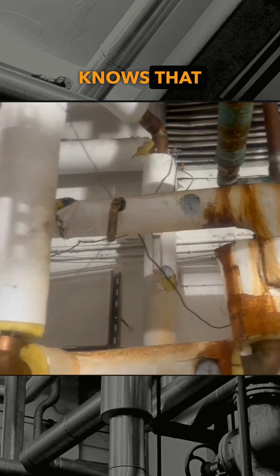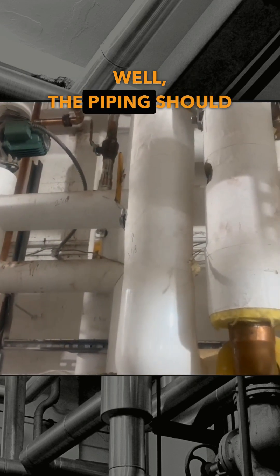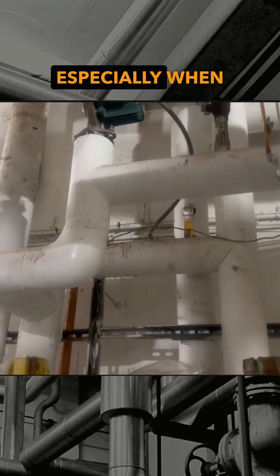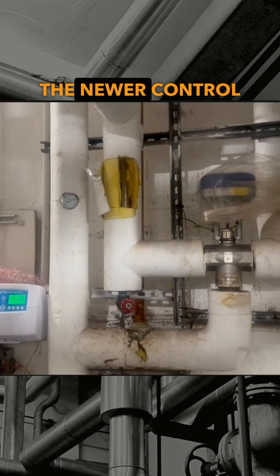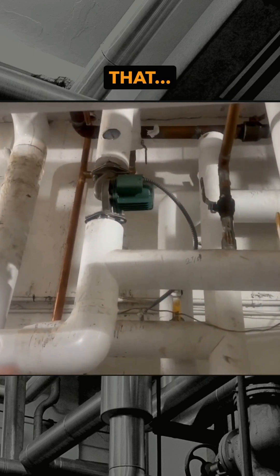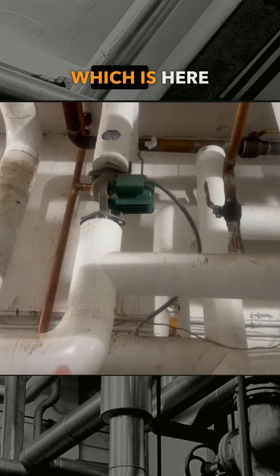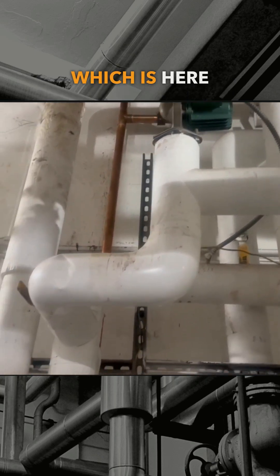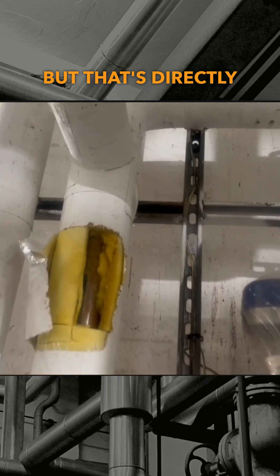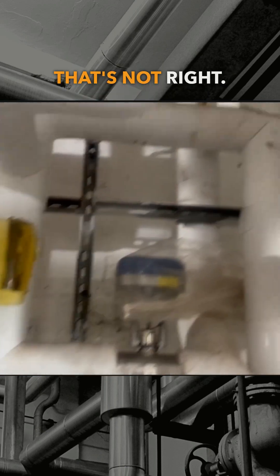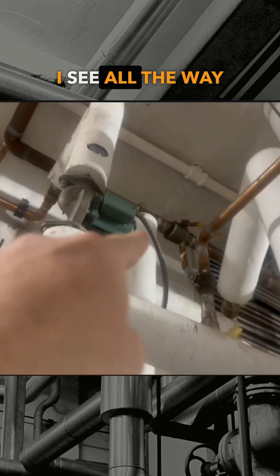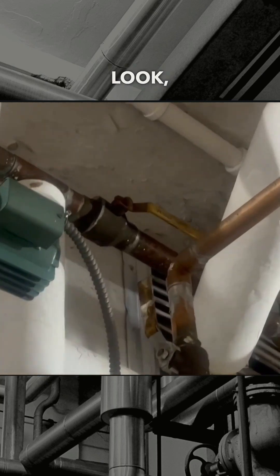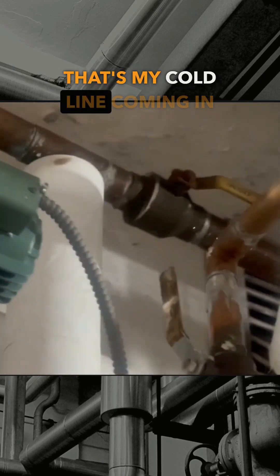that the piping, especially when you change to the newer control - the domestic line which is here is teed in here, but that's directly into the mixing valve. That's not right.